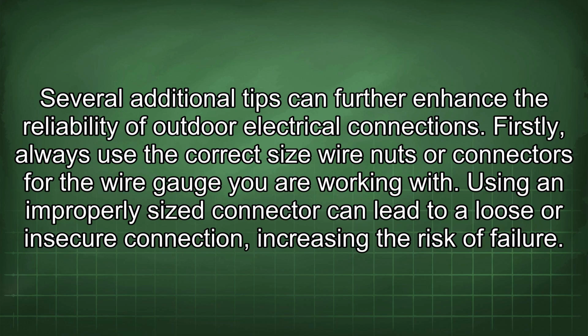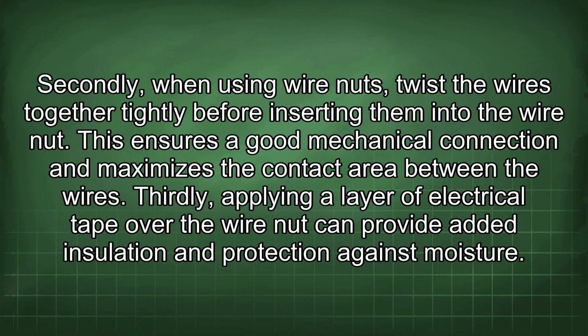Firstly, always use the correct size wire nuts or connectors for the wire gauge you are working with. Using an improperly sized connector can lead to a loose or insecure connection, increasing the risk of failure. Secondly, when using wire nuts, twist the wires together tightly before inserting them into the wire nut. This ensures a good mechanical connection and maximizes the contact area between the wires.